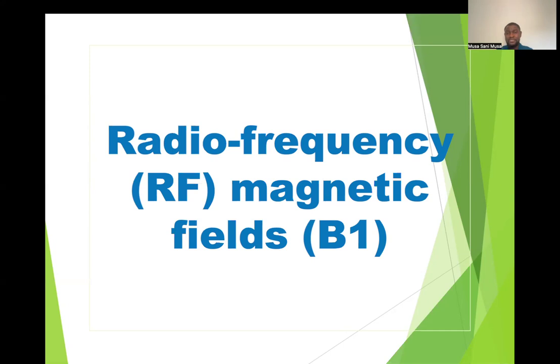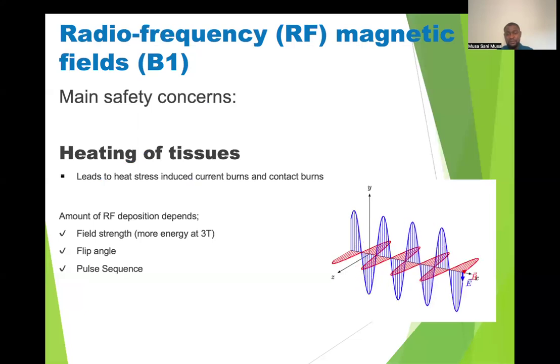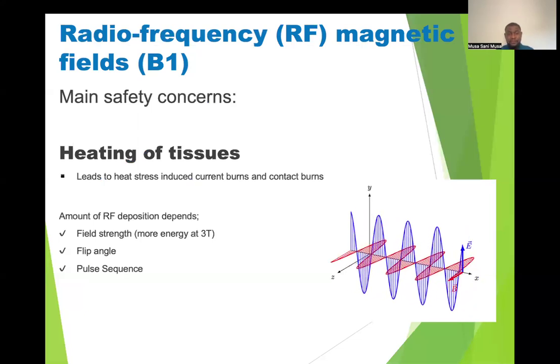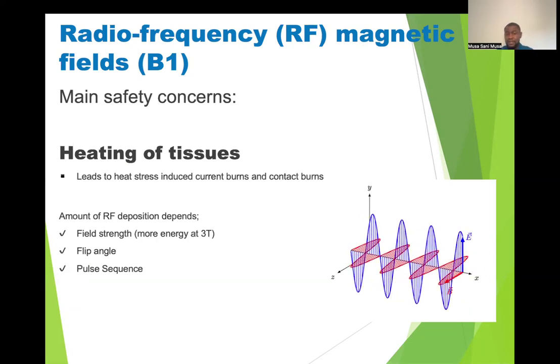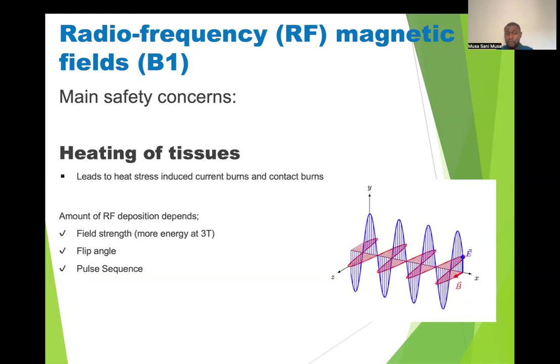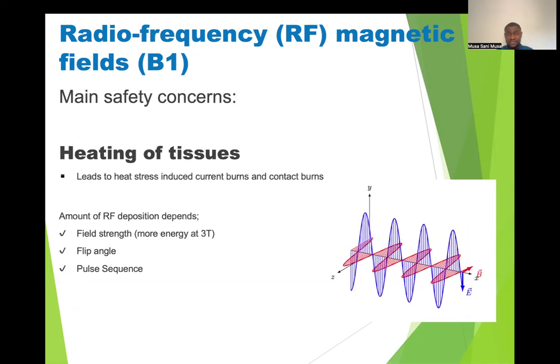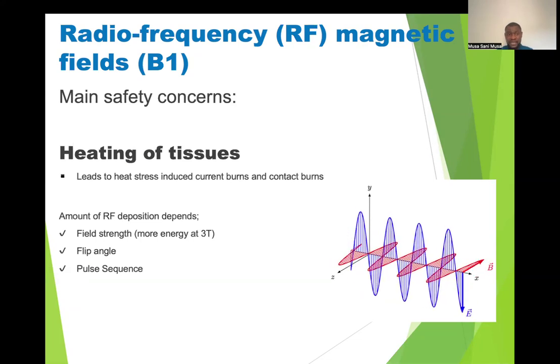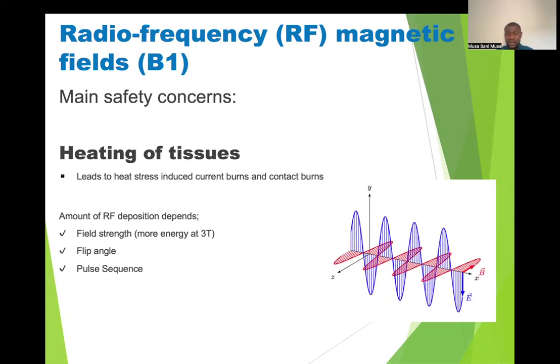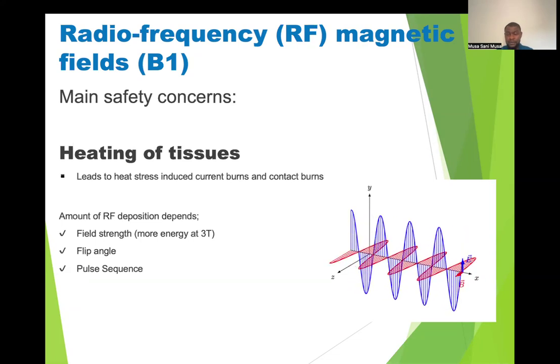So with RF now, because it's sending an RF pulse into the body, our radio frequency wave, we all know, is part of the electromagnetic spectrum. So it's sending some RF energy into the body. As a result, there's what we call RF deposition, which depends on the flip angle, the pulse sequence, and the field strength. More energy is being deposited at higher field strength, 3 Tesla or 7 Tesla. Heating of tissues is the main safety concern with the RF magnetic coil.